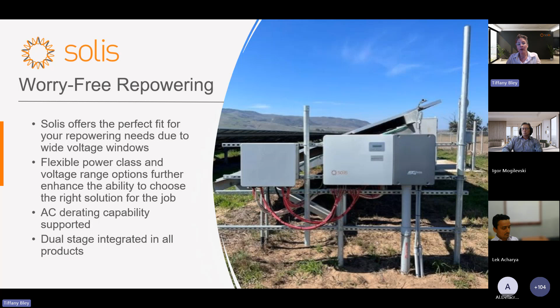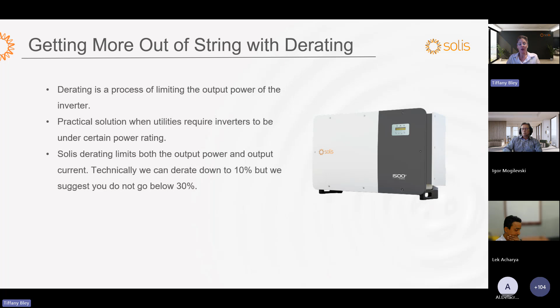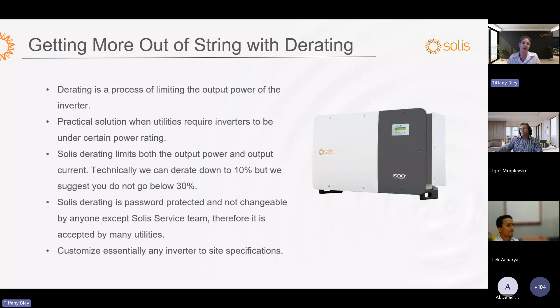On derating, this is a great offer from Solis. All of our products are capable of limiting the output power as well as the output current. It's a practical solution when utilities require inverters to be under a certain power rating. This is password protected, managed by Solis Service, and we can derate down to 10%, though we only recommend not going below 30%. We would provide a new label and a letter of derating, which means we can essentially customize any inverter to any site specification within our portfolio.